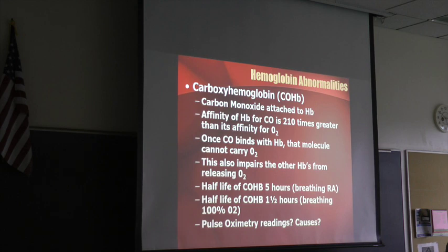How do you want to write that in your notes? What did you write, Julie? Danger, COHB and HBO2 absorb the same wavelength of light and inaccurate reading. Perfect. You want to write that? You have something different? What did you write? That was good. I just can't believe she wrote all that so quick. Can you say it again? Yeah. Danger, COHB and HBO2 absorb the same wavelength of light, inaccurate reading. Okay, I'll settle that.